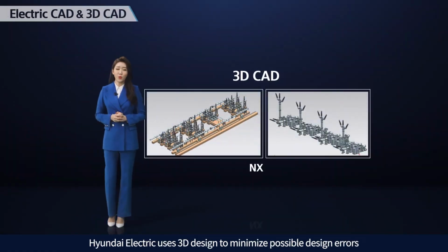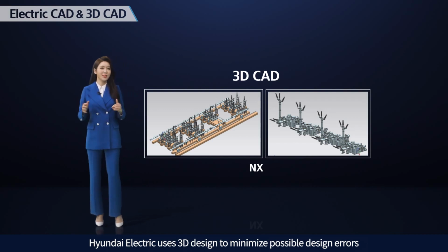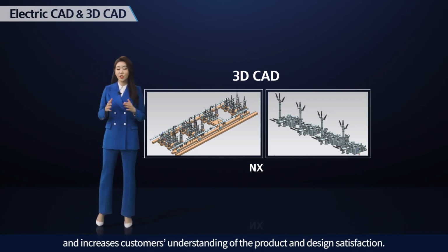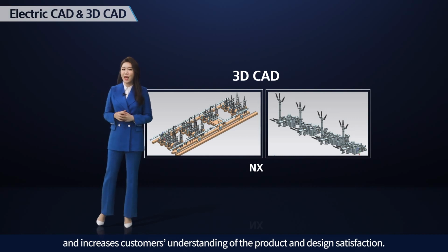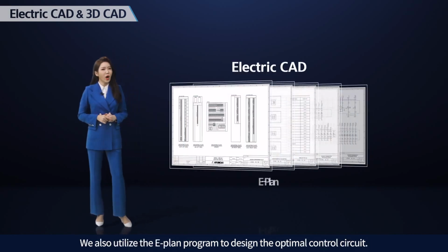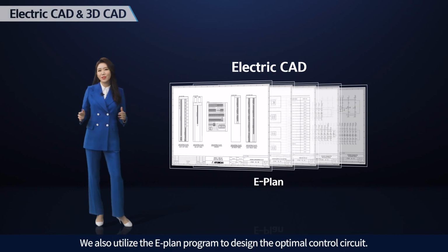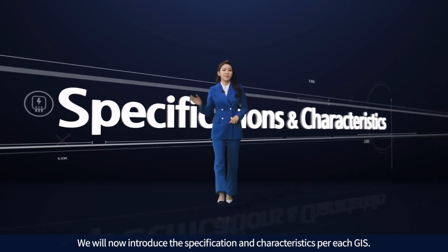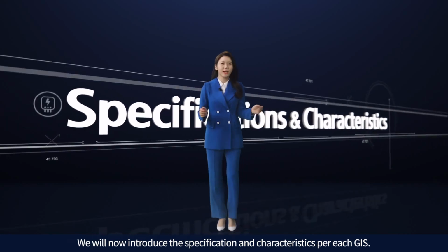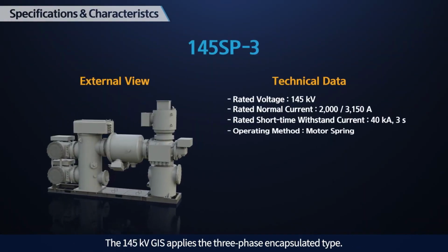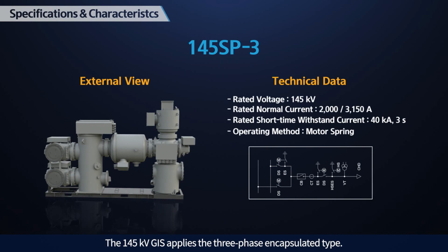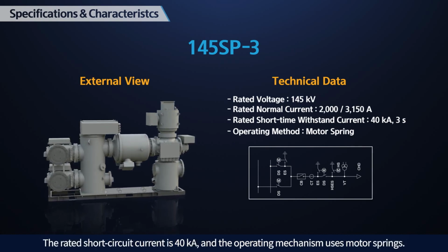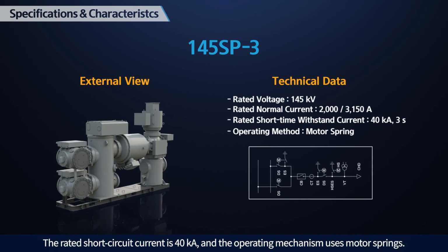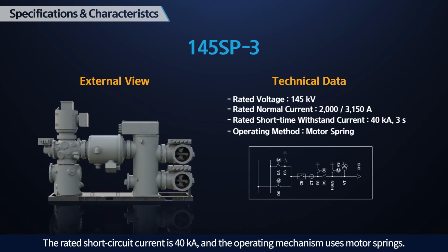Hyundai Electric uses 3D design to minimize possible design errors and increases customers' understanding of the product and design satisfaction. We also utilize the E-Plan program to design the optimal control circuit. We'll now introduce the specification and characteristics per each GIS. The 145 kV GIS applies the three-phase encapsulated type. The rated short circuit current is 40 kA, and the operating mechanism uses motor springs.